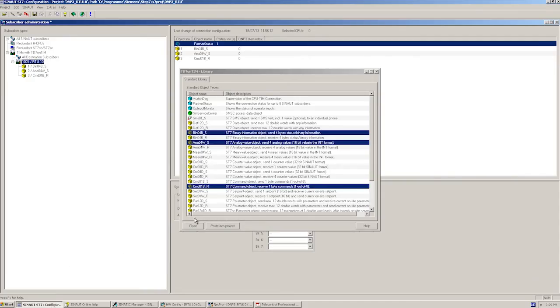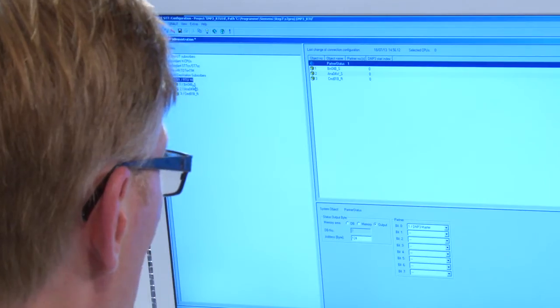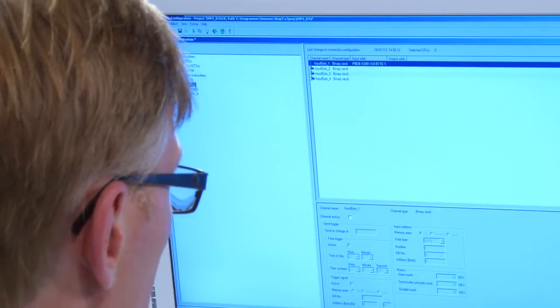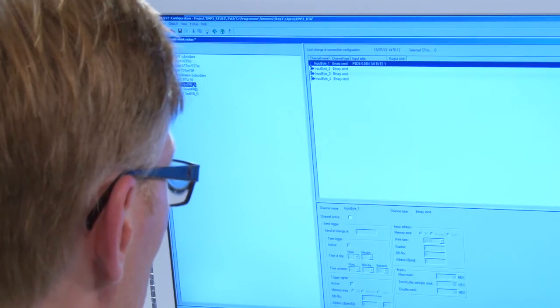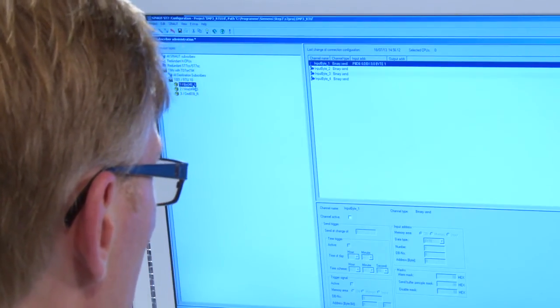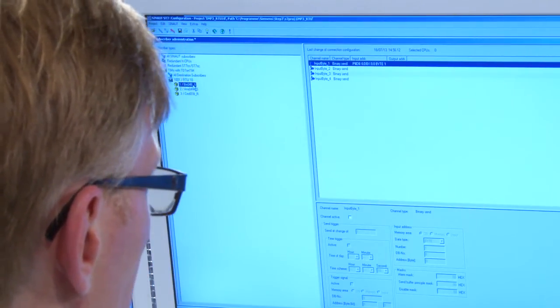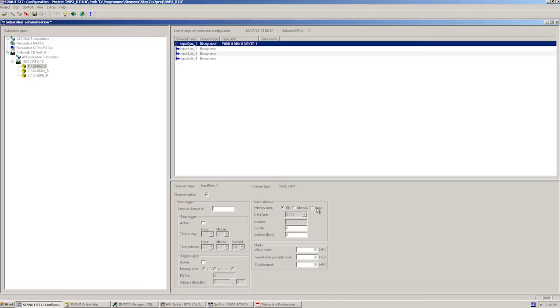We close the library and start the detailed configuration of the data point objects. First, we activate the first of four channels of the message block and specify the source address, from which the message or alarm will originate. In our example here, it is input byte 4 of our simulation module.